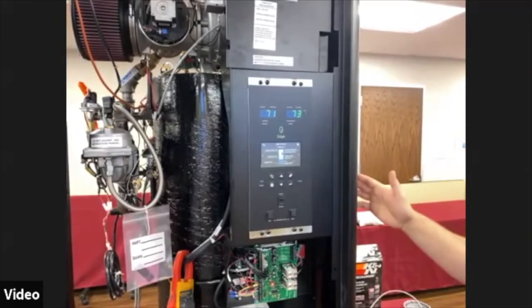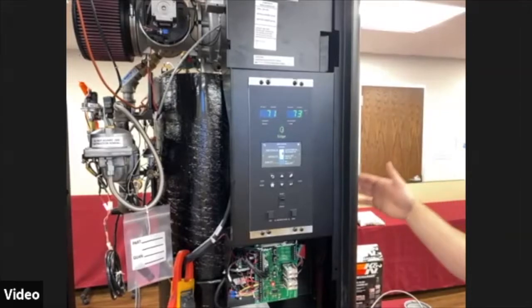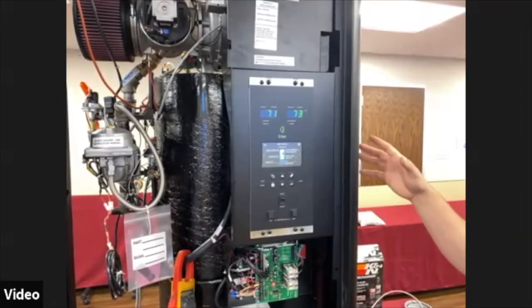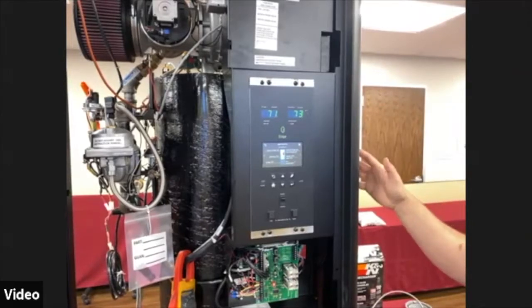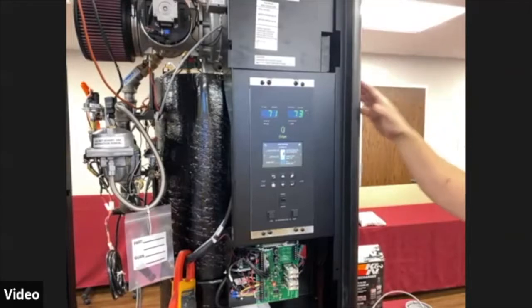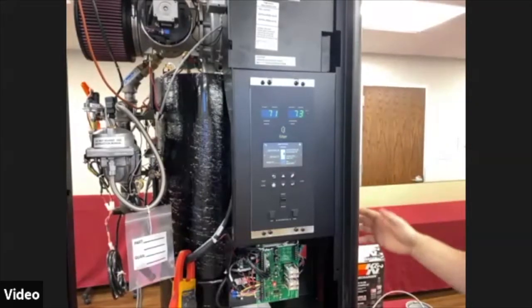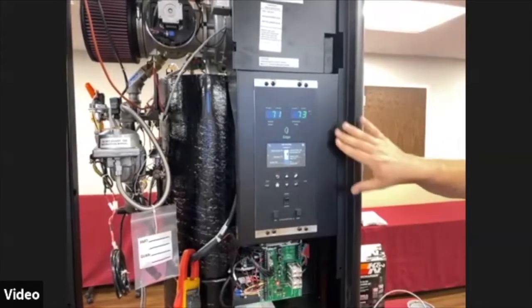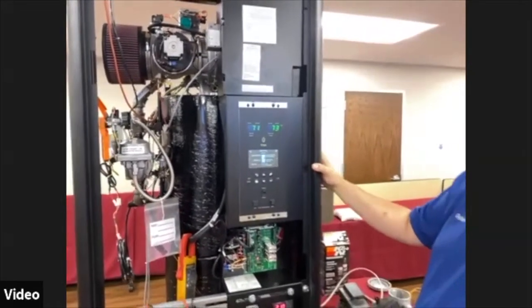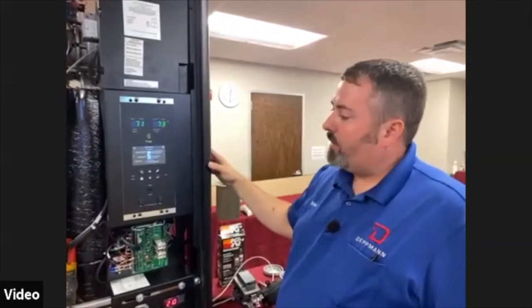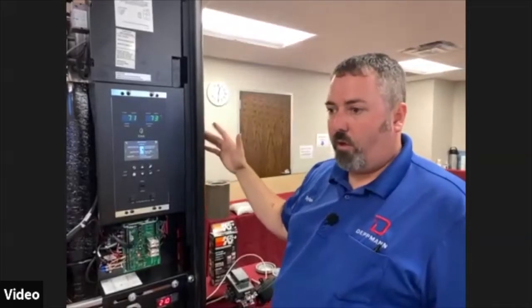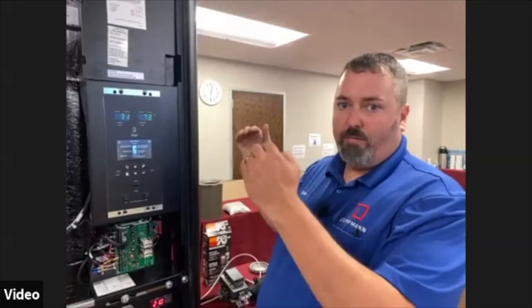So it'll fire the lead boiler first, whichever one is lead, and it'll go through the whole firing sequence that I just went through with you. Once that boiler is through its warm up and released, it'll ramp up. Once the lead boiler hits 50% fire rate, it'll initiate the second boiler. That's all, like I said, determined within the managing boiler, which boiler would be next. Once that boiler goes through its firing sequence, establishes flame and is released to run based on set point, both boilers will come to an even set point, which is usually in the 30% range, and they will ramp up together. Once both boilers hit 50%, again, it'll bring in the third boiler. You can run up to 16 boilers in a boiler plant with the Aerco Edge Controller.